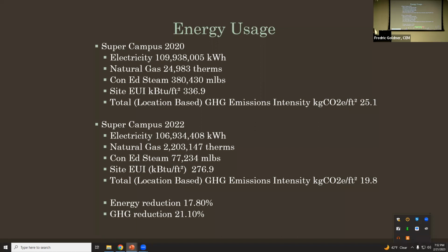When I first started at MSK 17 years ago, it was just baby steps. First we went after the chiller plant, then we interconnected everything. Then we went after the air handlers. We did Aircuity to do demand ventilation control. We're able to take the ORs in off hours, unoccupied, from 25 air changes down to about 6 air changes, and with Aircuity we were still able to make sure the rooms were in a ready state. We've also put it into the vivariums and our labs: in the vivarium we took air changes from 15 down to 8, and in the labs from about 12 down to 3 and 4. Most of the labs now are thermally driven instead of just ventilation driven. Overall, since 2007, we're down about 40% in energy usage for that 2.4 million square feet.